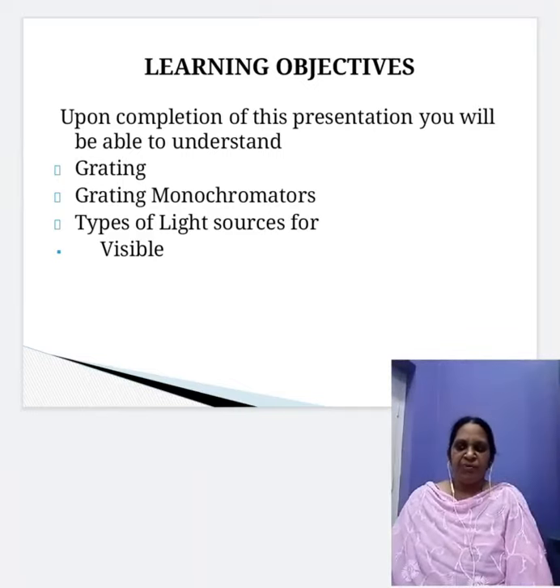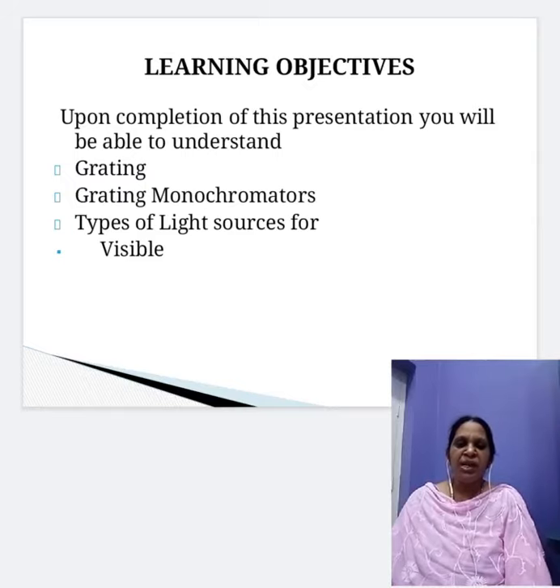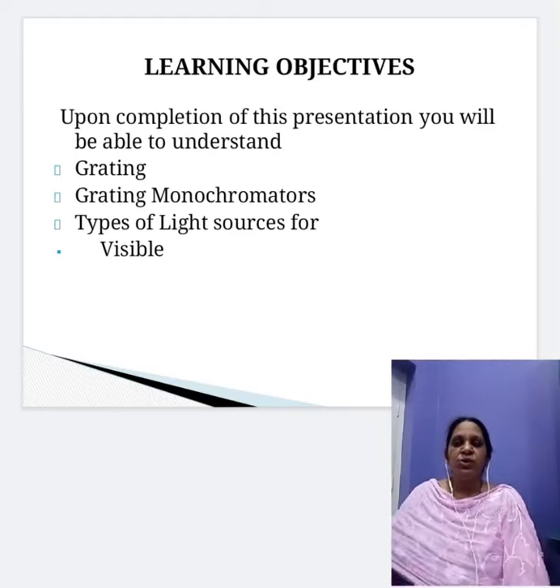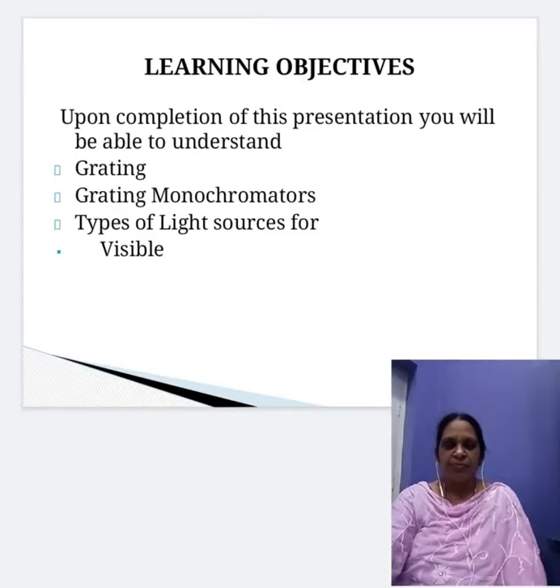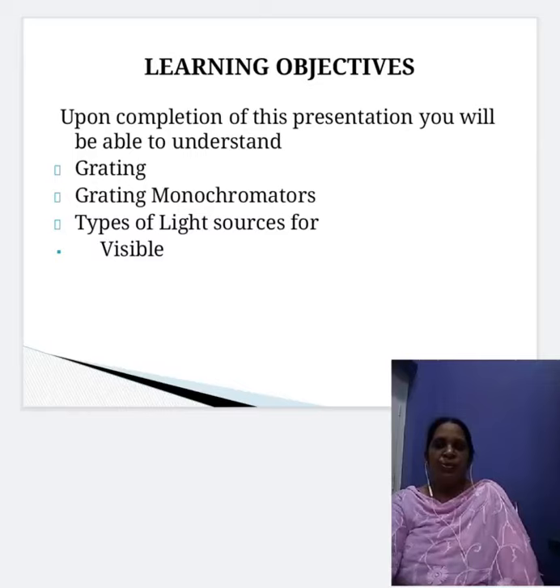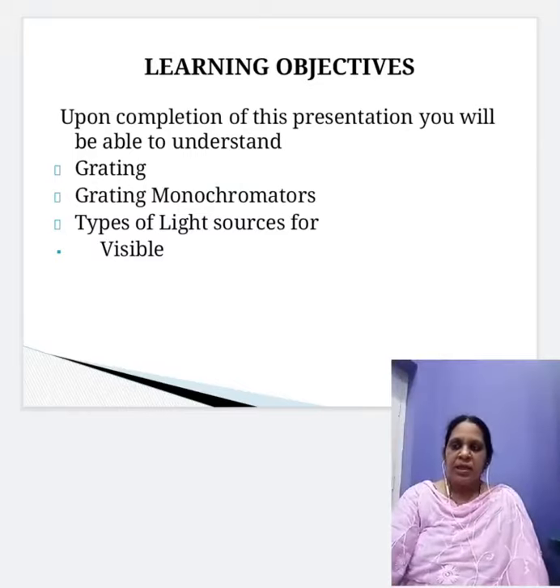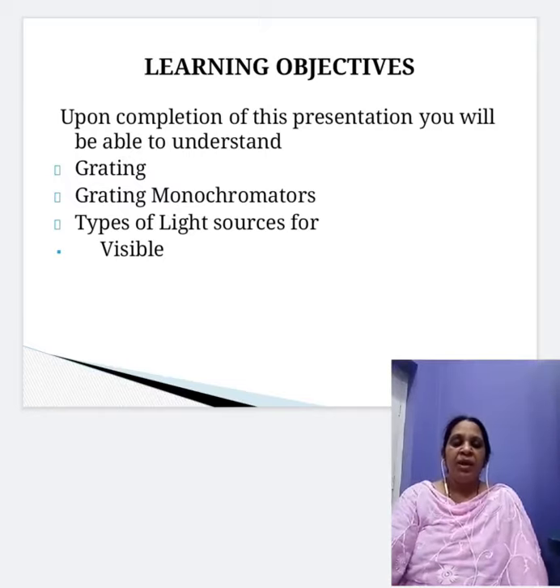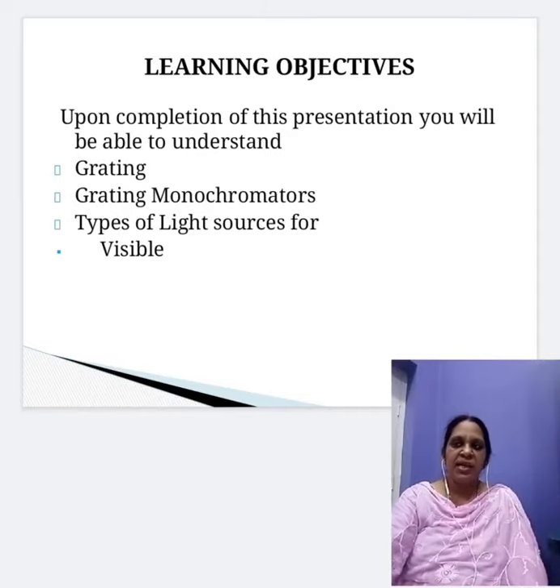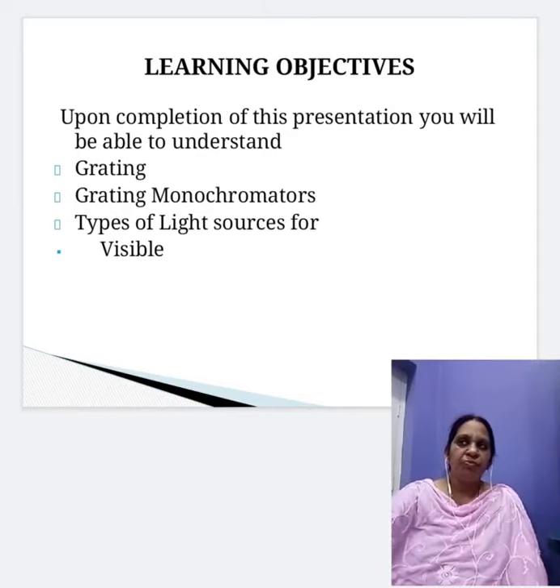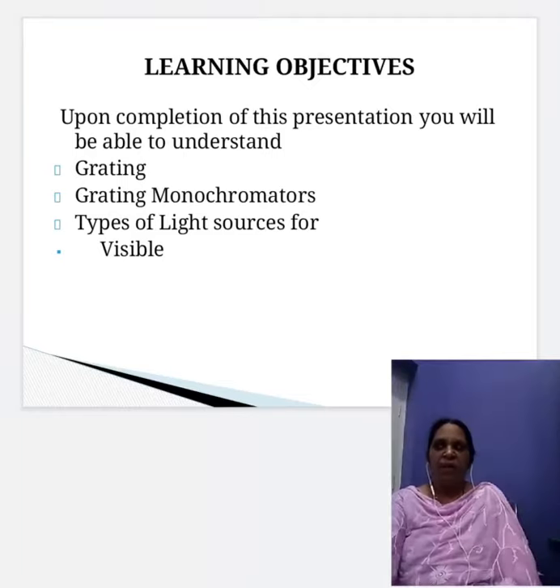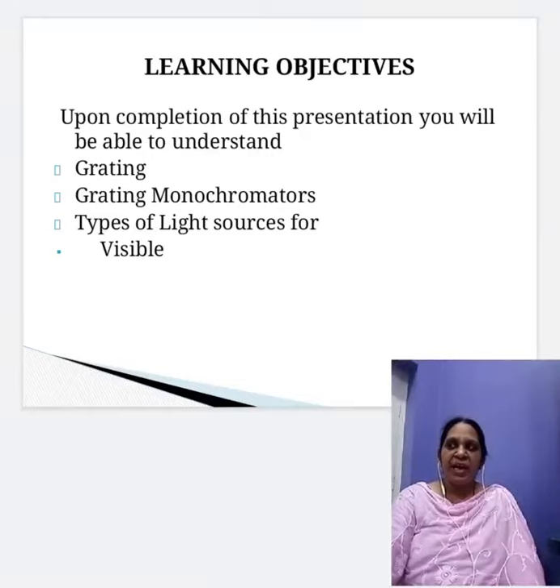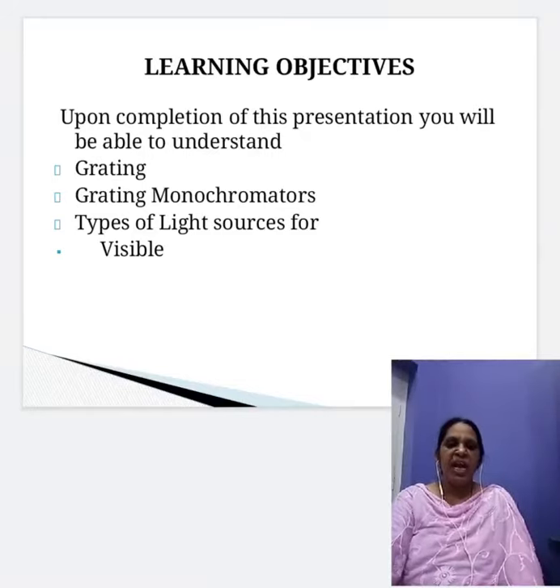Before going to discuss about grating, let me recap what is a monochromator. A monochromator is an optical device which is used to isolate a narrow band of wavelengths. It consists of an entrance slit, collimator, grating or prism as the dispersive medium, then a focusing lens and the exit slit. The primary function of a monochromator is to provide a beam of radiant energy of given nominal wavelength and spectral bandwidth.